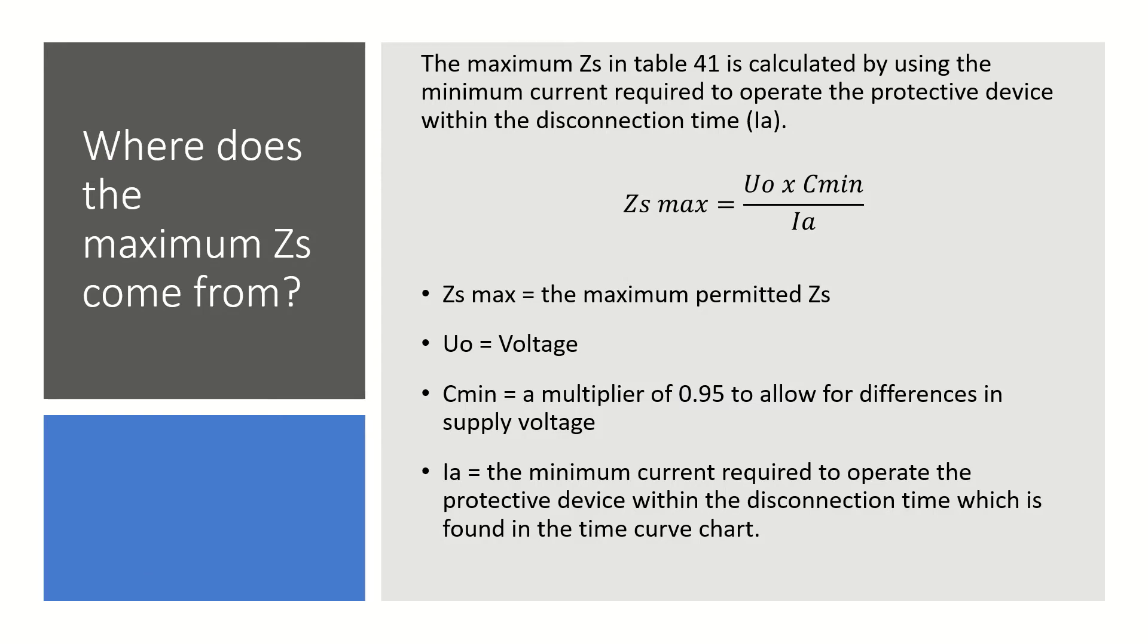So the first question is, where does the maximum Zs come from? The process for calculating the maximum Zs is explained in Appendix 3 of BS7671. The values are calculated by multiplying the voltage by Cmin, which is a correction factor of 0.95 to allow for differences in supply voltage, and then dividing by the minimum current required to operate the protective device, Ia.